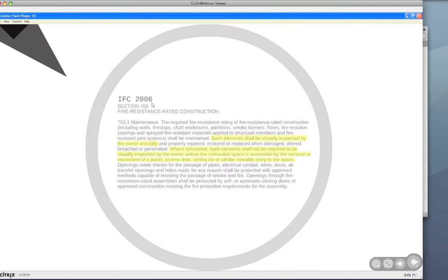Basically, according to section 703.1, fire resistance rated construction, including fire stopping, SFRM, etc., is required to be inspected visually by the owner annually. And if the elements are concealed, they do not need to be inspected unless the concealed space is accessible by the removal of a panel, access door, ceiling tile, or similar movable entries to the space. Now, this is quite a high impact change for the maintenance of buildings in general, and I'm sure facility managers listening are noting this change.